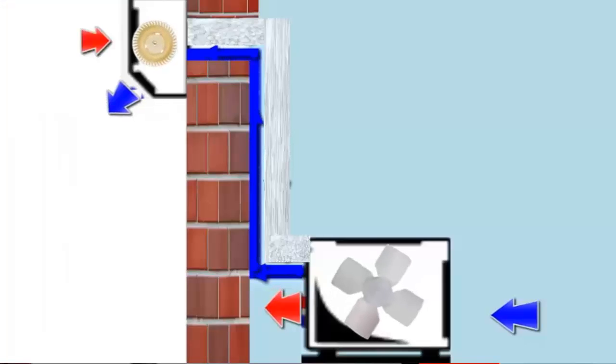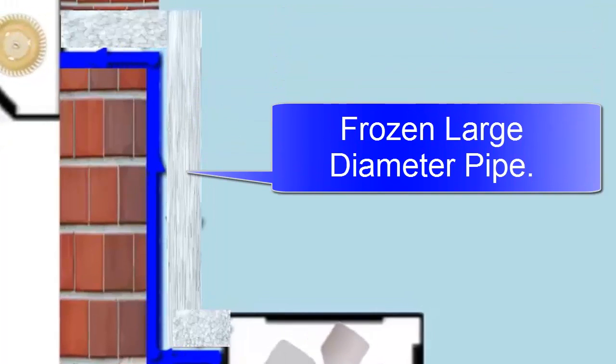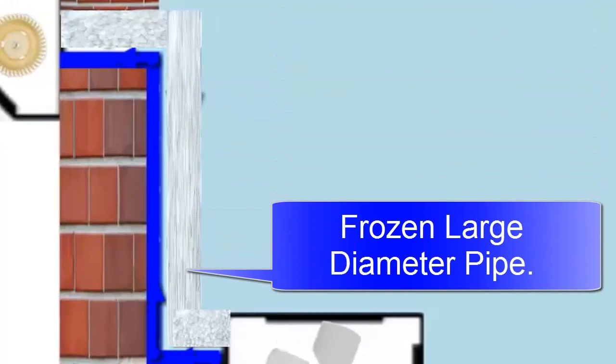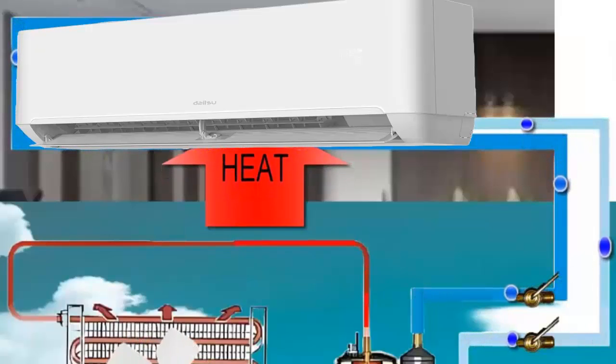9. If the thick or vapor pipe is freezing, the failure occurs in the evaporator. This is because the evaporator is responsible for supplying refrigerant to the thick pipe and receiving heat.